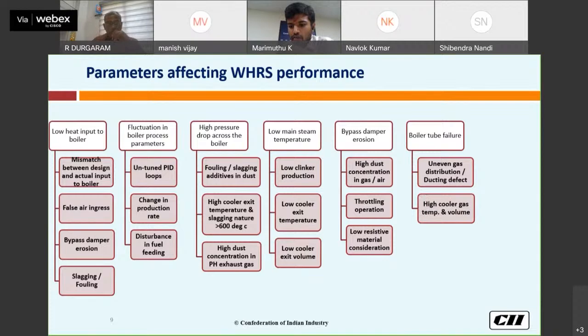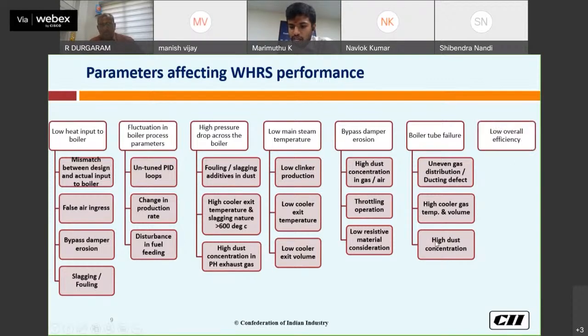And another one is high cooler gas temperature and volume. Suppose you want to operate the WHRS at 10% or 20% more than design; that will allow more flue gas. If the coils are not designed for that, we will have more velocity, and definitely it will cause erosion. And another one is high dust concentration, which we already discussed, and low overall efficiency.